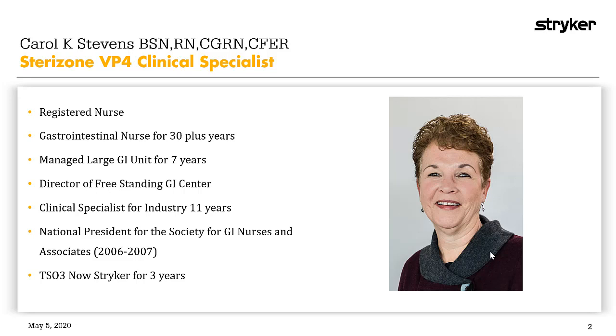Any non-compliance with guidelines or manufacturer protocols can lead to errors in reprocessing steps and can put the patient at risk for an infection. Sterilization eliminates all microbial life, including bacterial spores, providing a definite increase in safety margin. Both sterile processing departments and GI areas are always under pressure to turn over instrumentation and scopes to meet very busy OR and GI schedules. Meeting turnover requirements lends itself to human error in reprocessing. There is definitely a fine line between efficiency and reprocessing effectiveness for the safety of every patient.